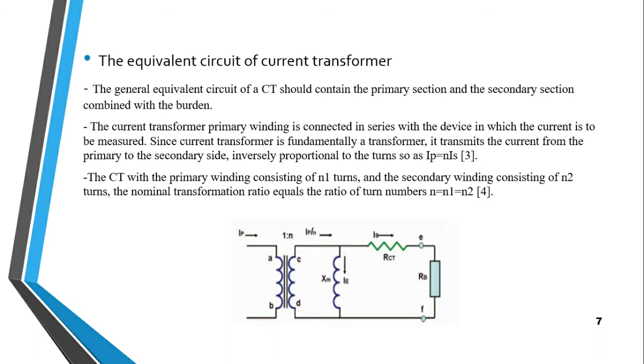Since the current transformer is fundamentally a transformer, it transmits the current from the primary to the secondary side inversely proportional to the turns, so IP equals N times IS. But other researchers said that the CT, with the primary winding consisting of N1 turns and the secondary winding consisting of N2 turns, has a nominal transformation ratio equal to the ratio of turn numbers, N equals N1 equals N2.